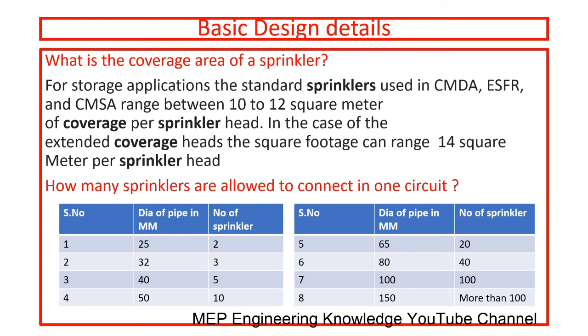Two sprinklers can be connected in a 25 mm dia pipe. Similarly, 3 sprinklers can be connected in 32 mm dia, 5 sprinklers in 40 mm, 10 sprinklers in 50 mm dia, 20 sprinklers in 65 mm dia, 40 sprinklers in 80 mm dia, 100 sprinklers in 100 mm dia, and more than 100 sprinklers in 150 mm dia. This is how the sprinklers have to be connected. If you connect 3 sprinklers in a single 25 mm dia pipe, the pressure or the water flow can't be achieved as per the requirement. So we need to be very careful while doing execution and testing.